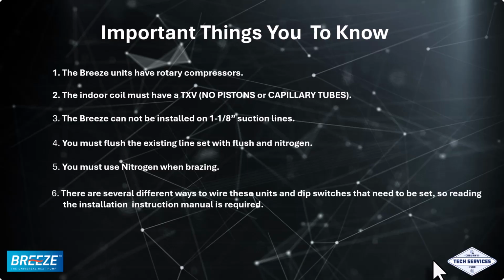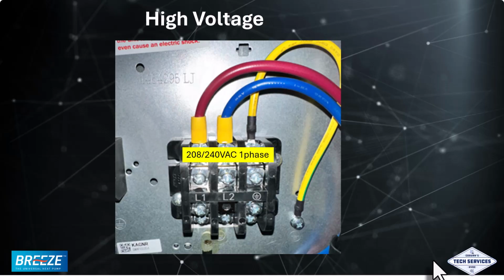There are several ways to wire these units and set the dip switches, so reading the installation manual is required. Needle point meter leads are required for troubleshooting due to the small wire connections. High voltage wiring, 208, 240 volt, you have L1, L2, and ground.